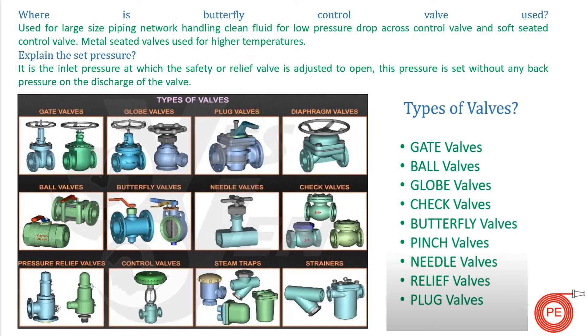The next question is: what is a butterfly control valve? A globe valve is one type of control valve, but in many cases we don't use globe valves because they are very large in size and costly. Butterfly valves with actuation are used as control valves in large-size piping networks. They are used in low pressure drop areas, with soft-seated types for lower temperatures and metal-seated for higher temperatures. For clean fluid and low-pressure networks — including gases with very low pressure — butterfly valves are used as control valves.